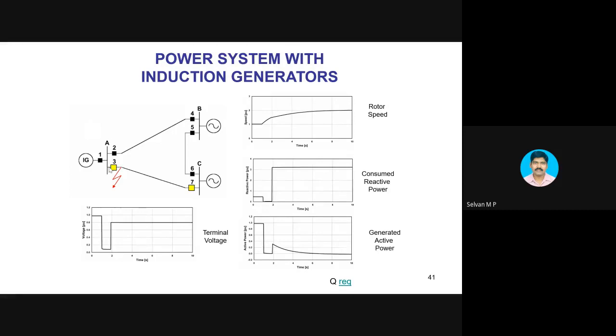Again, to understand that, we have to go to the torque slip characteristics of the squirrel cage induction machine. We will not touch upon that here. A squirrel cage induction machine can operate only within a narrow slip. Though we say that above synchronous speed it acts as a generator, you cannot operate a 1500 RPM machine at 1600 RPM. It won't generate any real power. So here the speed increases enormously because the reactive power consumption increases, and though the speed is more, it cannot supply any active power to the grid.